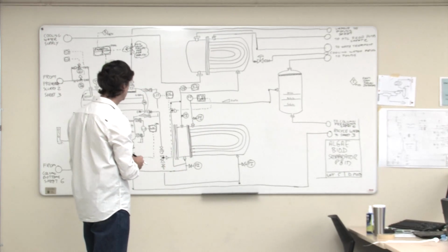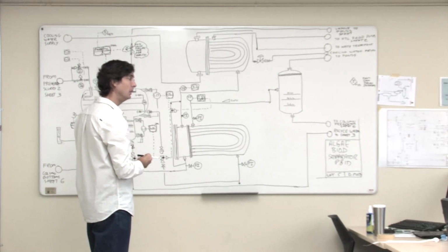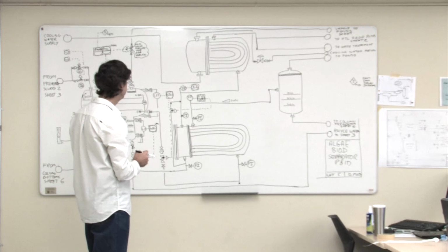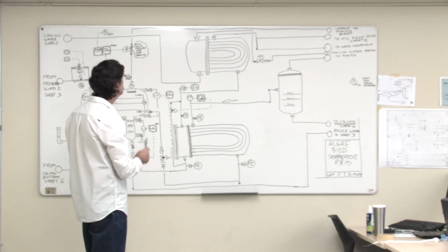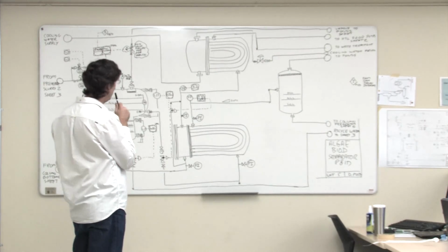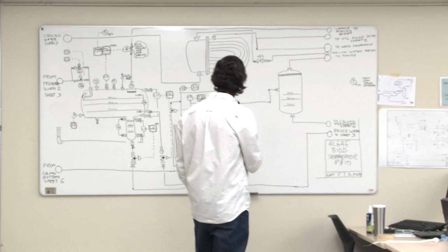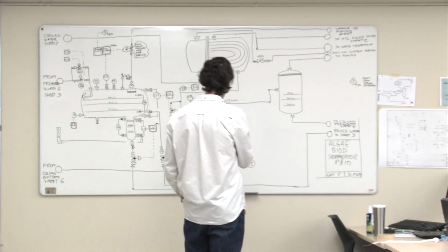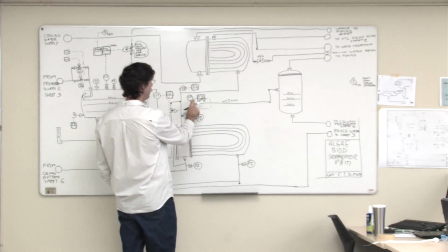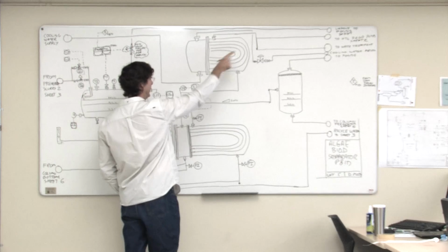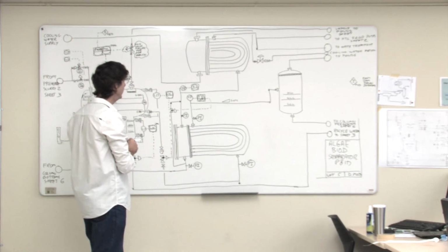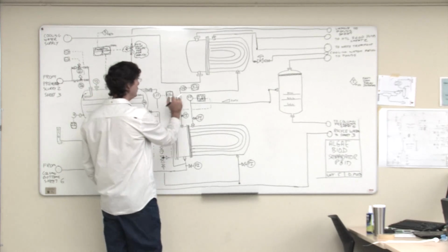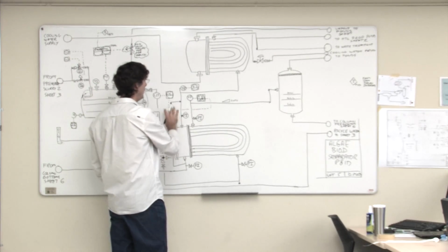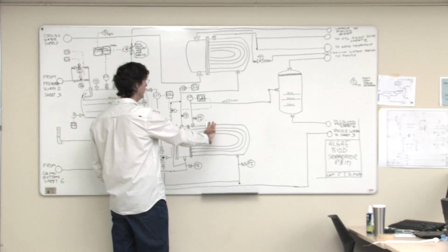Do you always bypass the tubes? Now you can bypass either side, it doesn't matter. Is there one where you usually choose a bypass for, like the more important stream or something like that? It's a good question, Jay. The next heat exchanger, you can control that with as much as you want to, you can just use cooling water. Yeah. So you might as well bypass it on that stream if you don't really care about this temperature. Yeah, that's why I'm putting the controller on this stream here for sure, because that one I can control with that heat exchanger. Yeah, the bypass, you're going to end up changing these two temperatures together when you open and close that bypass. So whether I put the bypass on this stream or on that stream, I don't think it really matters.